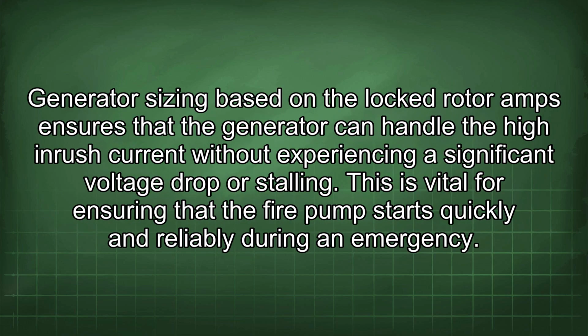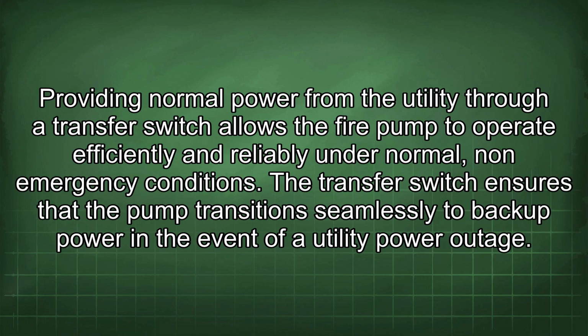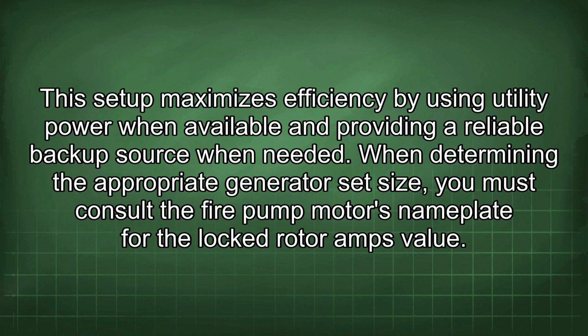Generator sizing based on the locked rotor amps ensures that the generator can handle the high inrush current without experiencing a significant voltage drop or stalling. This is vital for ensuring that the fire pump starts quickly and reliably during an emergency. Providing normal power from the utility through a transfer switch allows the fire pump to operate efficiently and reliably under normal, non-emergency conditions. The transfer switch ensures that the pump transitions seamlessly to backup power in the event of a utility power outage. This setup maximizes efficiency by using utility power when available and providing a reliable backup source when needed.